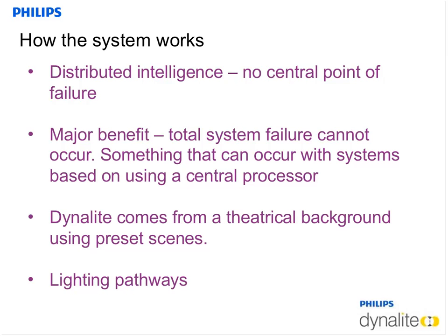With Dynalite, the intelligence is loaded onto the devices that are dotted around the installation. So if you have a failure, the system can, for the most part, continue to operate. And of course, you can diagnose much more quickly if you have distributed intelligence. So we don't have a central processor. We can be confident that we have a secure system. And again, when you go back to the casino in Sydney, you can imagine how powerful this message is somewhere where security is very, very high on the agenda.